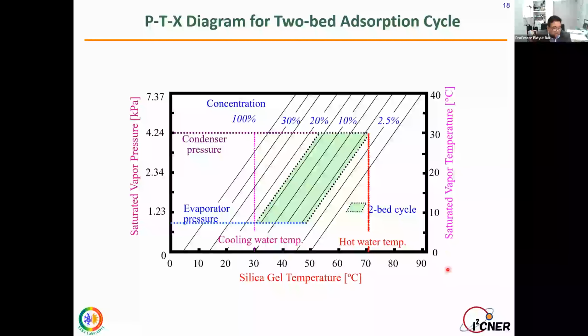So how do things work here? This is a little bit of the technical part. We take the diagram of the thing. This is our adsorption happening in this case. Here we have the silica gel percentages of about 17.5 to 2.5. In our preheating mode, our desorption, moisture is going out from the bed from 17.5 to 2.5%. Then here we have the pre-cooling for 30 seconds. No concentration difference is happening, it only cools down. And then our adsorption is happening here, temperature not changing, but the amount of moisture increases in this cycle.